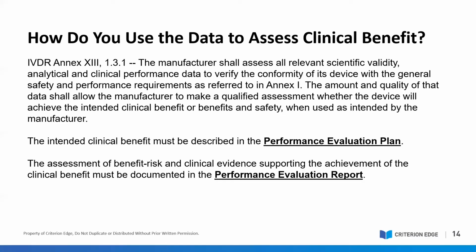In IVDR Annex XIII, 1.3.1, they state that the manufacturer shall assess all relevant scientific validity, analytical, and clinical performance data to verify conformity of the device with the general safety and performance requirements. And the amount and quality of that data, and quality gets back to that appraisal, shall allow that manufacturer to make a qualified assessment as to whether that device will achieve the intended clinical benefit when used as intended.